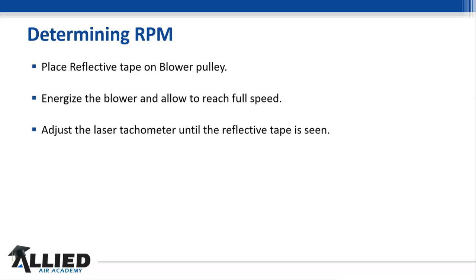So we're going to put reflective tape on the blower pulley. One of the most common mistakes that I see is people want to get the blower motor RPM. Well, they put it on the blower motor pulley, and if it's a 1800 or 3400 RPM, that's what you're going to get. So that's one of the things, and trust me, I've done it. When I first did this, I caught myself putting it there too. So we want to go to the blower pulley itself and put it on that pulley.